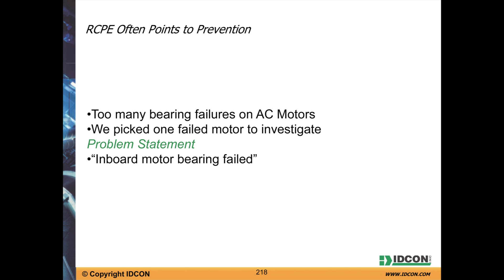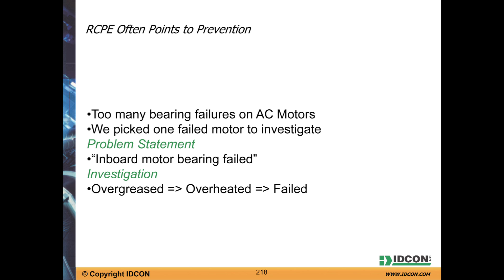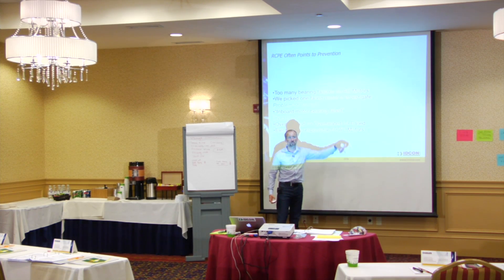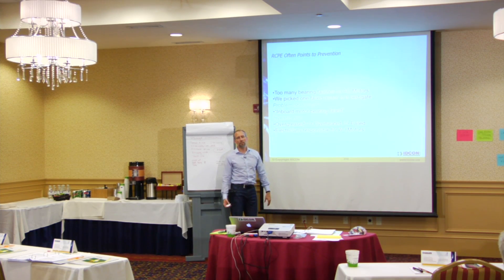We did the investigation and found the answer pretty quickly. We opened up the motor, looked at the bearing — it was over-greased, therefore it overheated and then it failed. The technical cause was fairly clear: we had over-greased it, it overheated and it failed. But we were wondering why did they over-grease the motor.